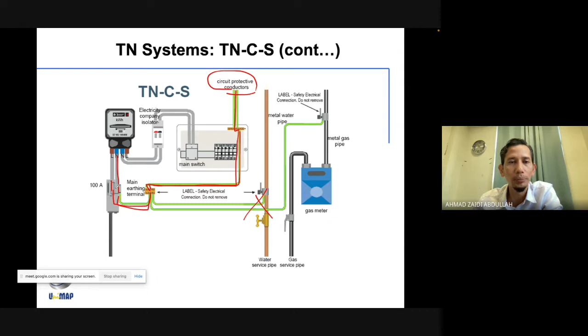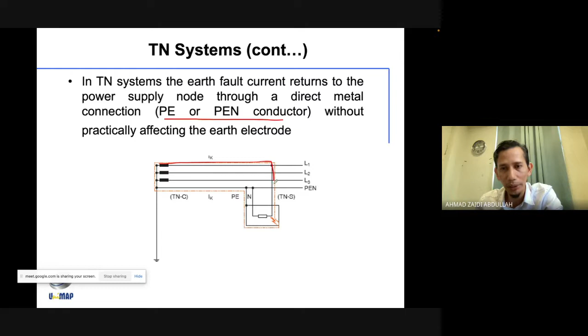In the TN system, the earth fault current returns to the power supply node through a direct metal connection - we call this the PEN conductor. So if there's a fault, it directly returns through this connection.